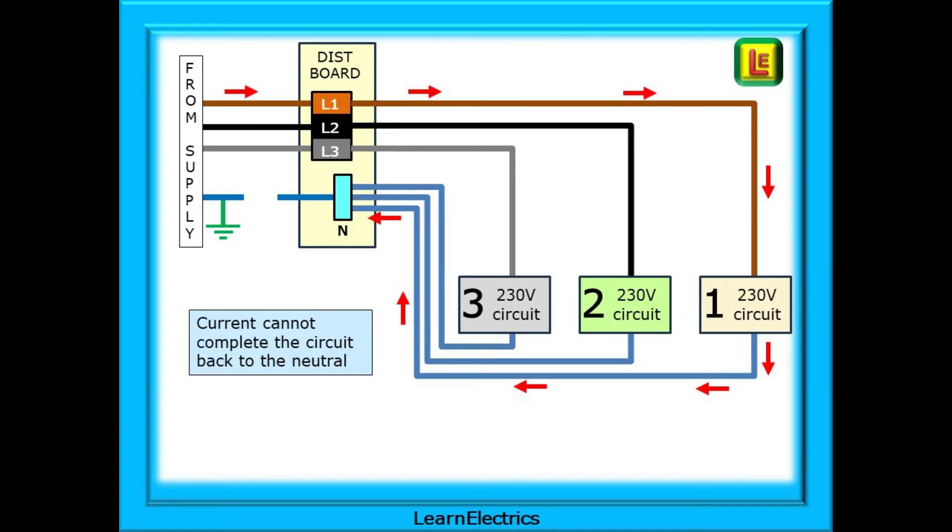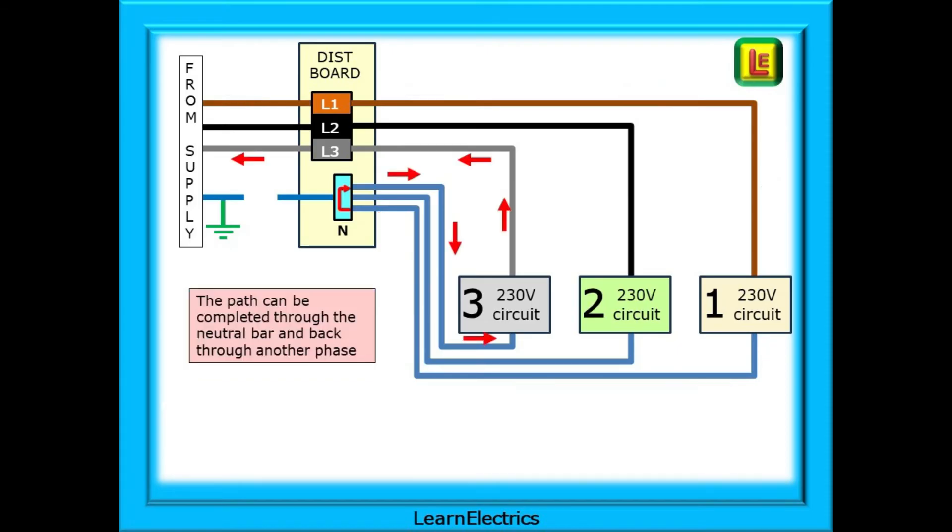The current cannot complete the circuit back to the neutral, but the electricity will try another path. It will always attempt to complete a circuit and find its way back to the source, back to where it came from, the supply transformer. And look, the path can now be completed through the neutral bar and back through another phase, L3 shown here. That is a path back to the source. It doesn't need the neutral connection and now our problems begin.